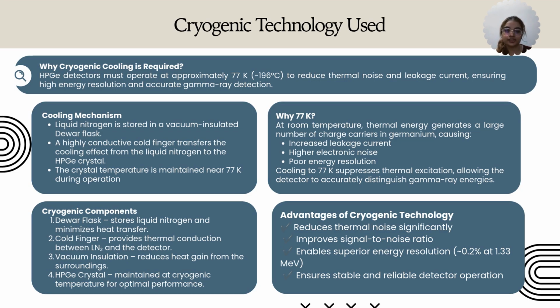The cryogenic technology used in HPGE detectors is liquid nitrogen cooling. This technology is essential because HPGE detectors cannot achieve their high energy resolution at room temperature. At higher temperature, the thermal energy generates excess charge carriers in the germanium crystal, which increases leakage current and electronic noise. To overcome this problem, the detector is cooled to approximately 77 Kelvin or minus 196 degrees Celsius using liquid nitrogen. The liquid nitrogen is stored in a Dewar flask which provides excellent thermal insulation.